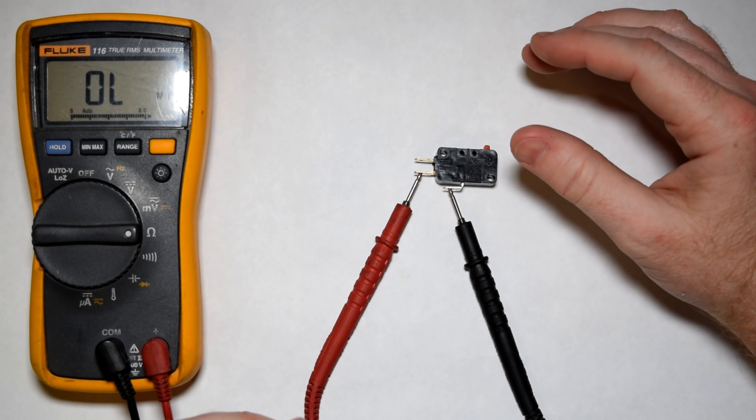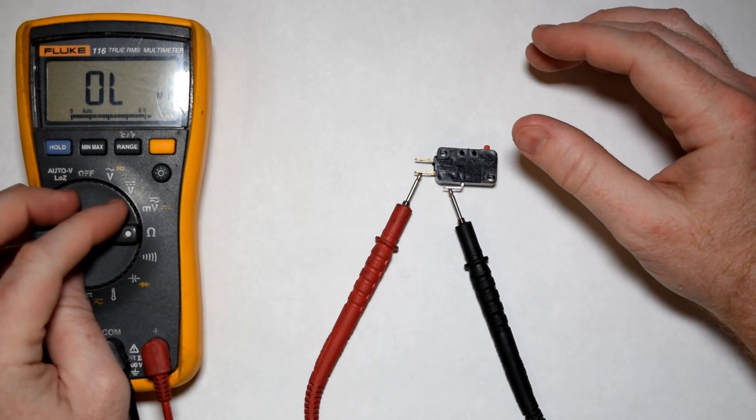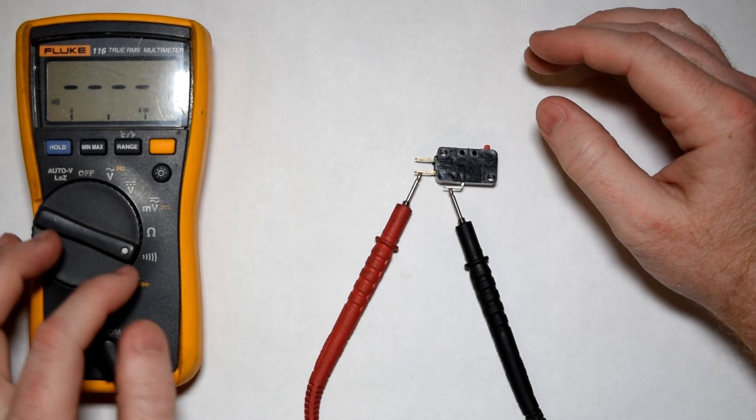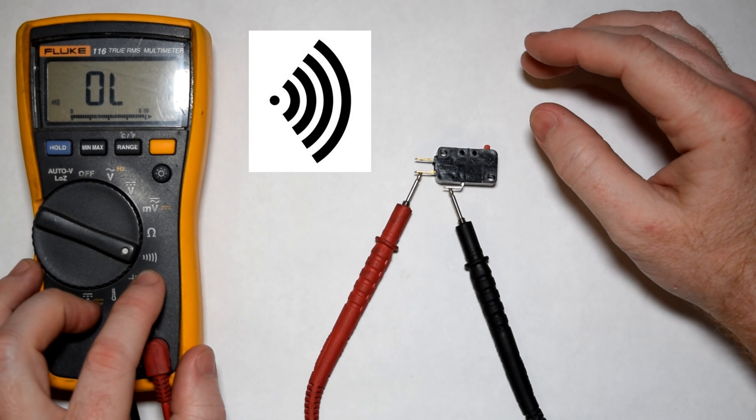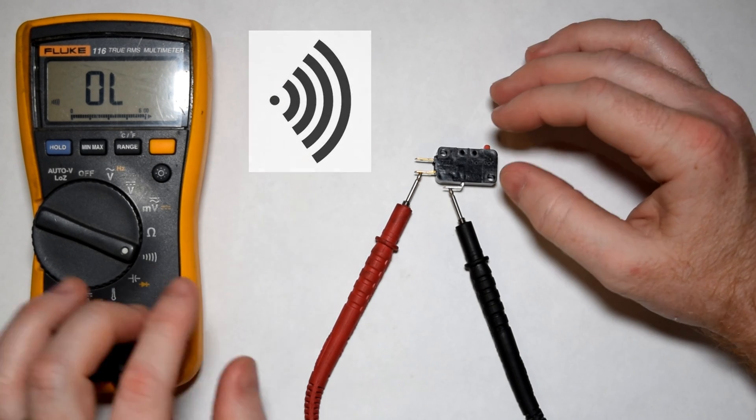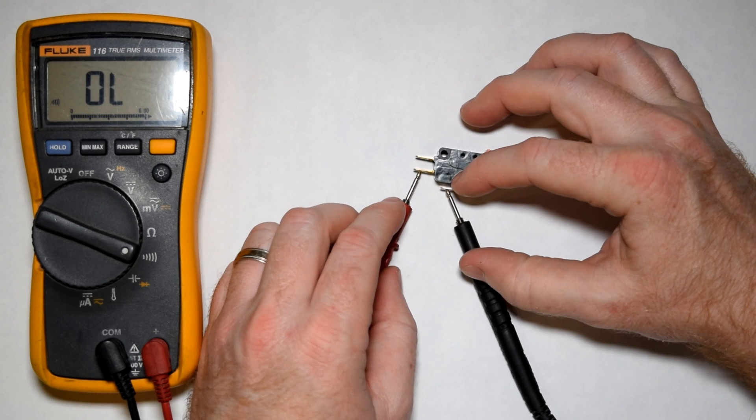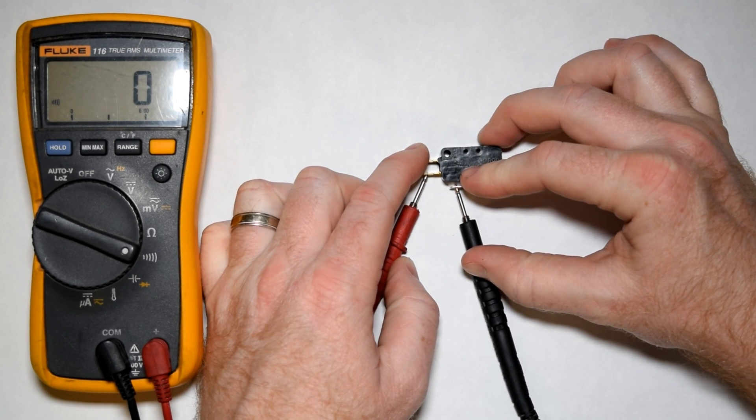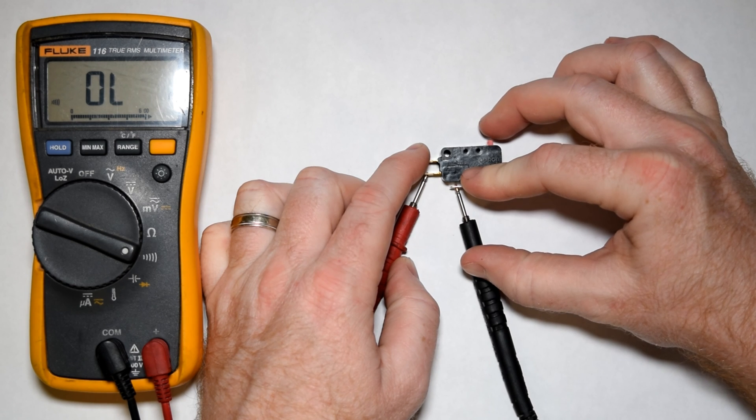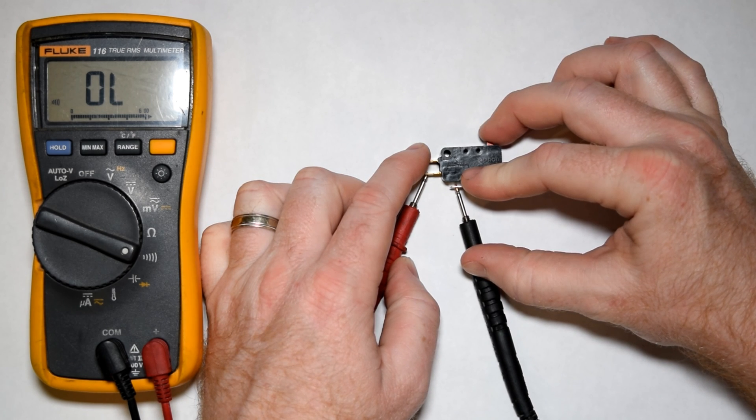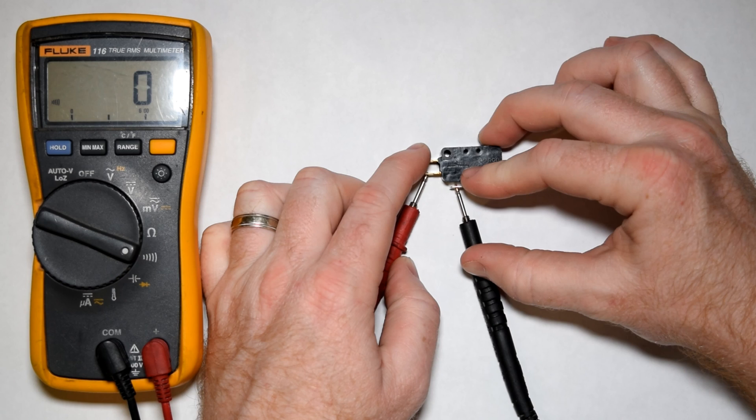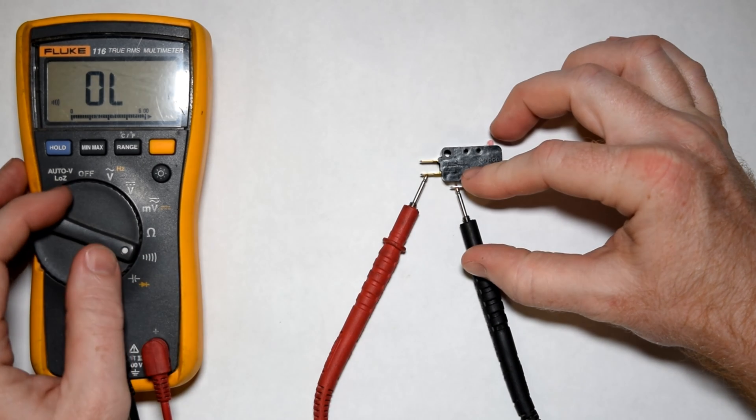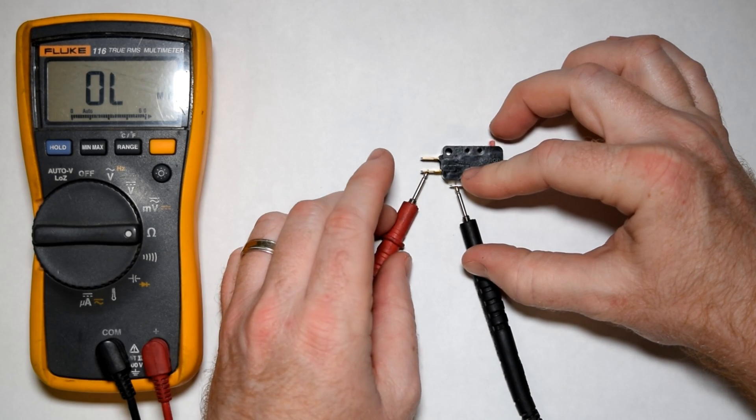Alternatively, this is the ohm test that we're doing. You can also, if your meter has this function, looks like a Wi-Fi symbol, this is the audible continuity test. So right now we're on the normally open circuit and we're going to depress the switch and you get an audible beep. But I want you to notice that it just gives you zero as the reading, does not give you as detailed of a ohms of resistance reading.